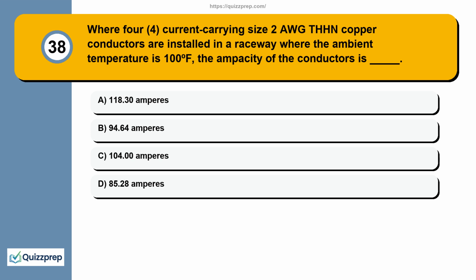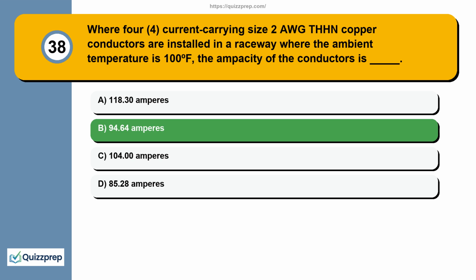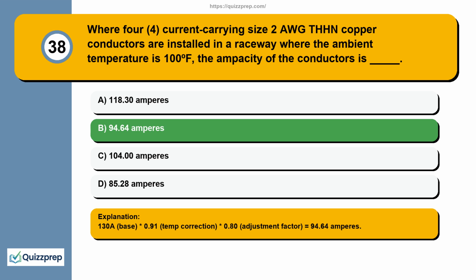Question 38. Where 4 current carrying size 2 AWG THHN copper conductors are installed in a raceway where the ambient temperature is 100 F, the ampacity of the conductors is: 118.30 amperes, 94.64 amperes, 104.00 amperes, 85.28 amperes. 130 A base, times 0.91 temperature correction, times 0.80 adjustment factor, equals 94.64 amperes.